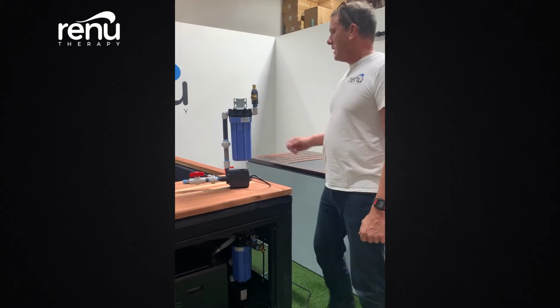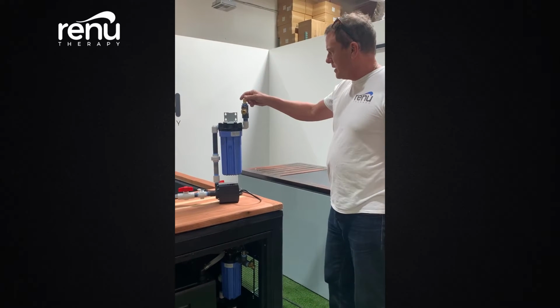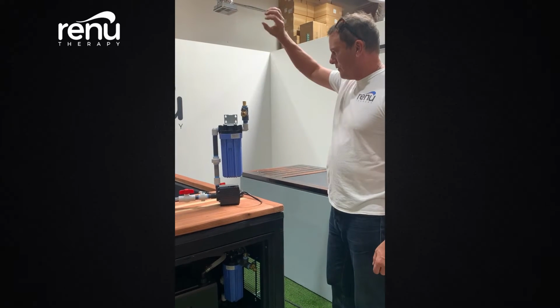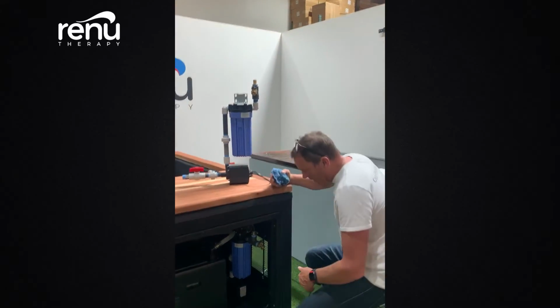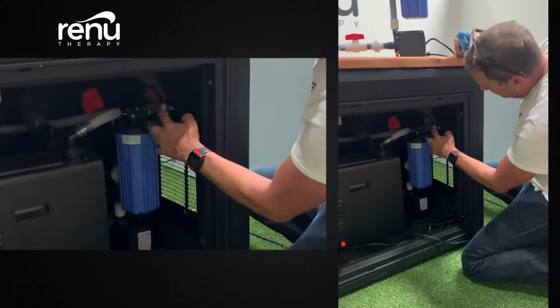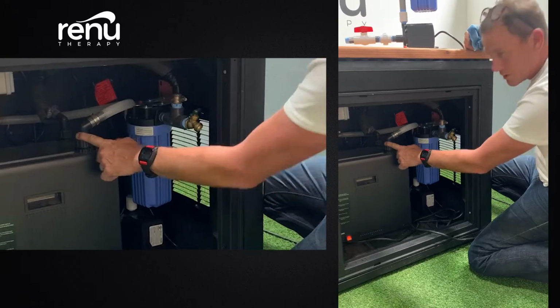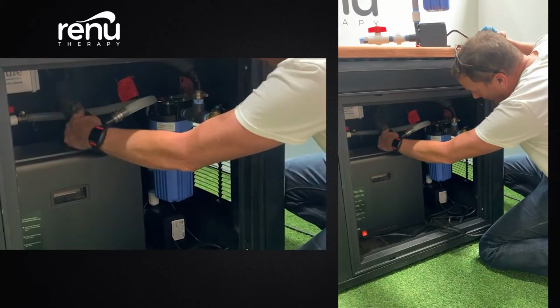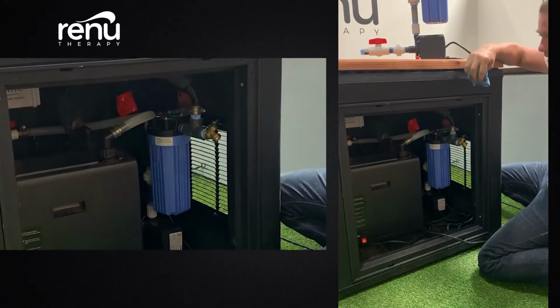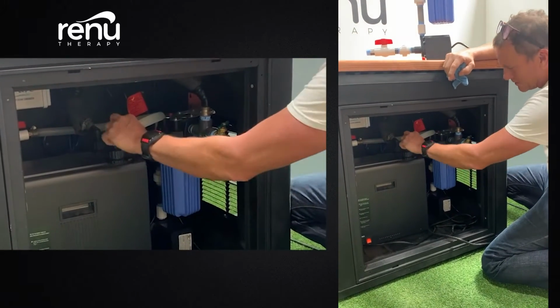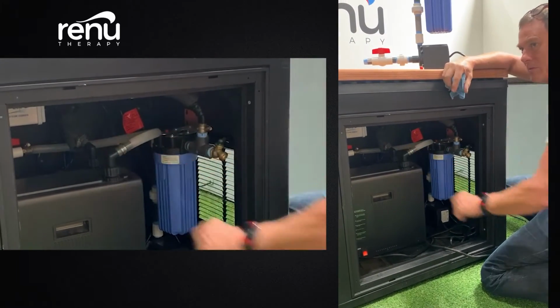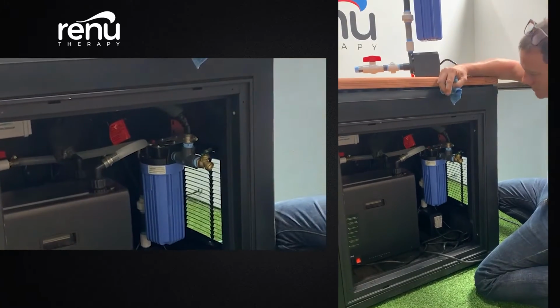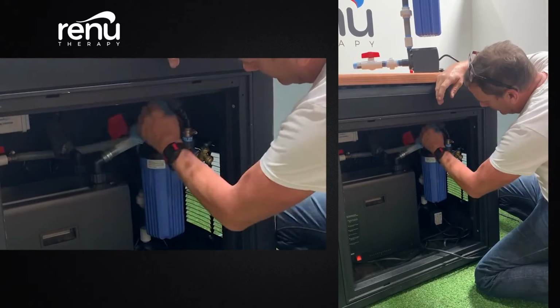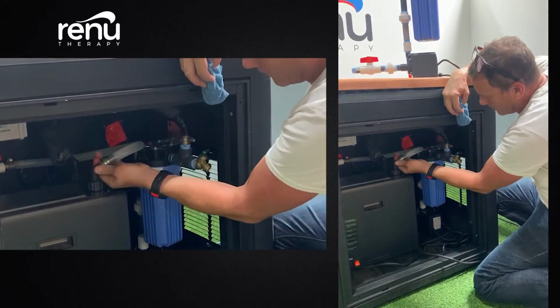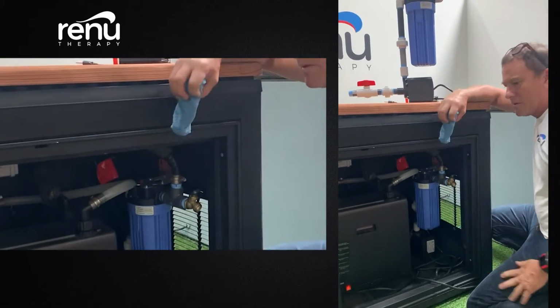Another thing that could be leaking is the hoses. The hoses come out from the filter housing, and if you look in here, there's a hose coming off the filter housing, going into the chiller and out of the chiller and into the tank. These hose clamps sometimes will leak a little bit, and they're really easy just to tighten back up. Once again, you dry everything off, find out where the culprit is, and then that's what you go ahead and fix.